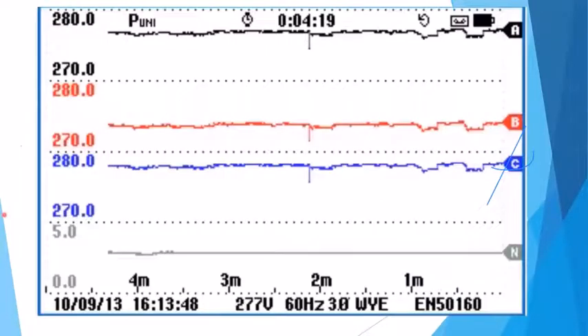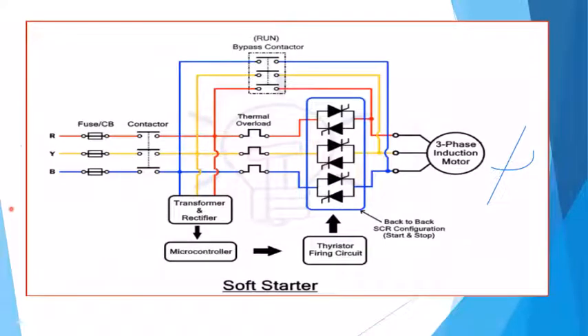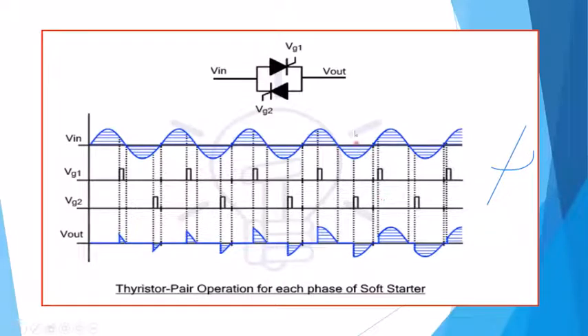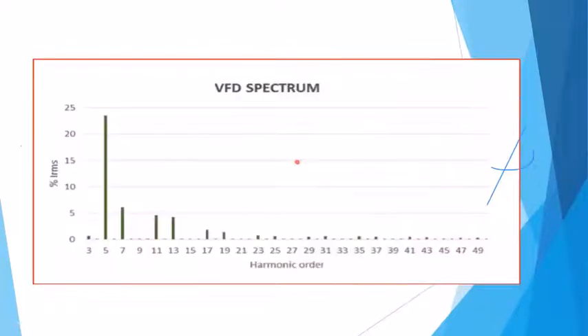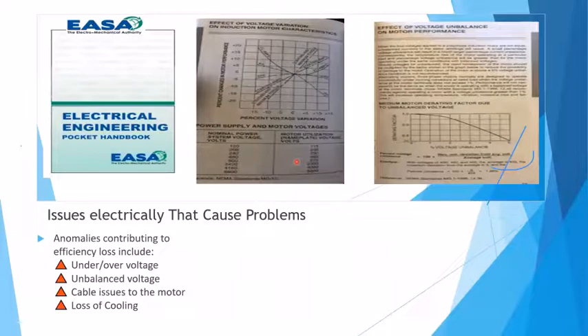So my belief is that a lot of pumping applications should be designed with soft starting technology, meaning that we can just trim off the waveform. They're also typically about half the price of a VFD. It accomplishes the soft starting so that you don't overload the power line or cause a lot of voltage drop as the motor comes up. That tends to be, in my opinion, still one of the better technologies. Plus, they're now designed so that if the motor is lighter loaded, it can bring the power down based off of current and lower the current feeding the motor. That was the original Nola patent done by NASA many years ago, and that's basically how the soft starter began.